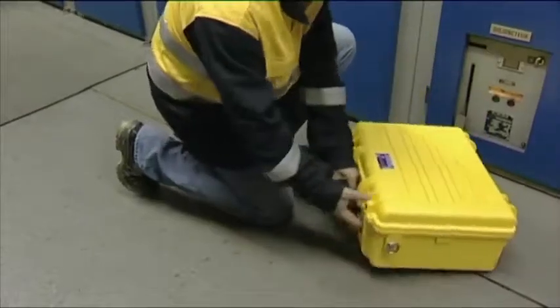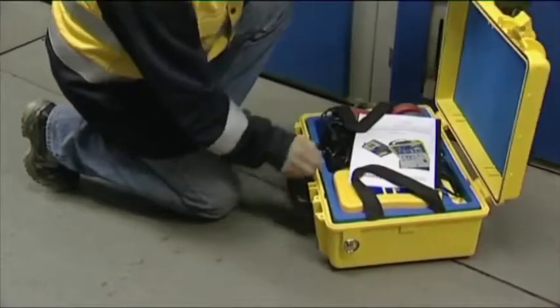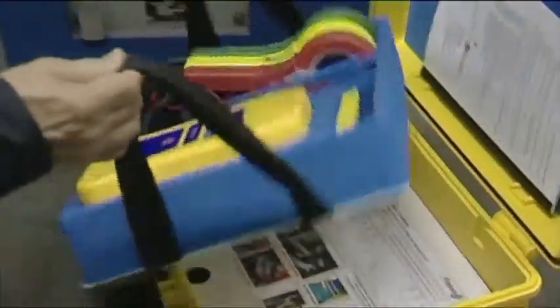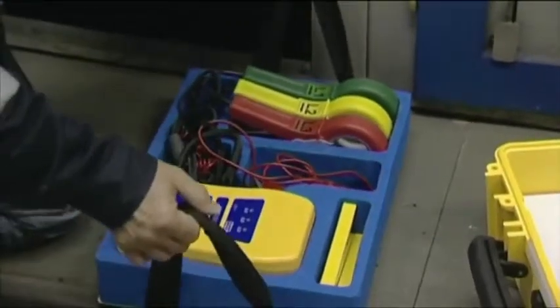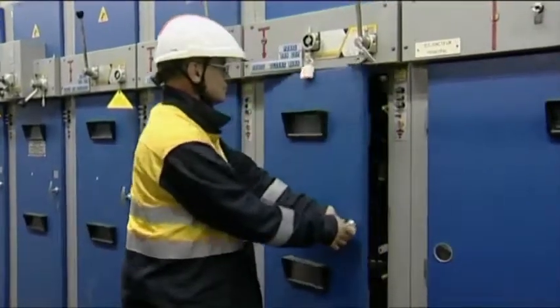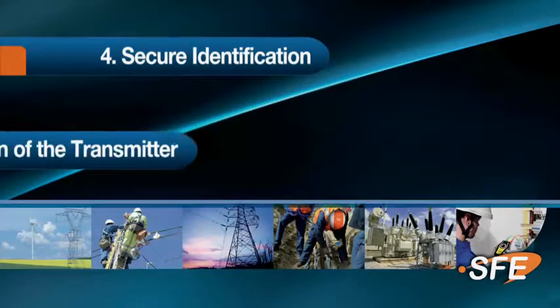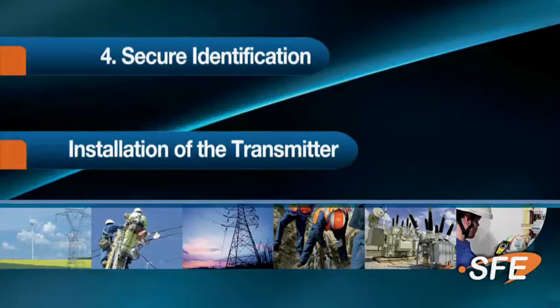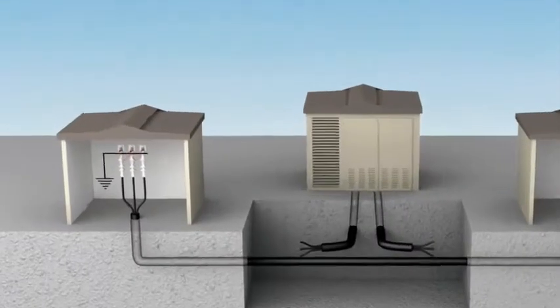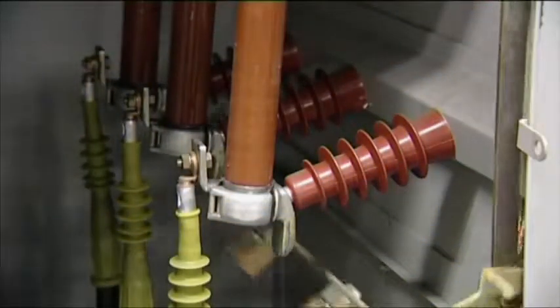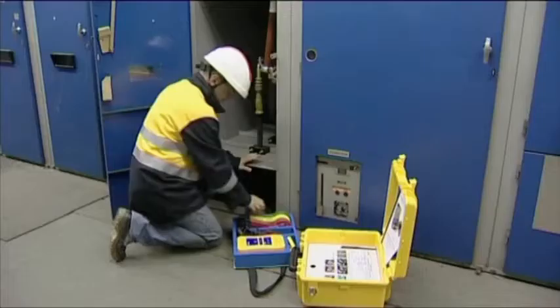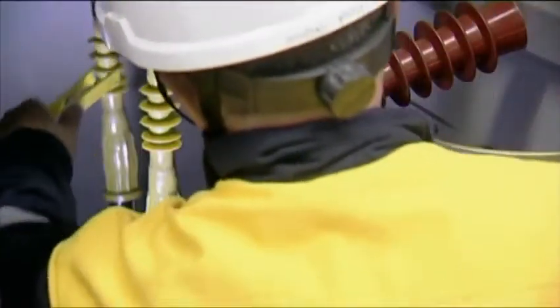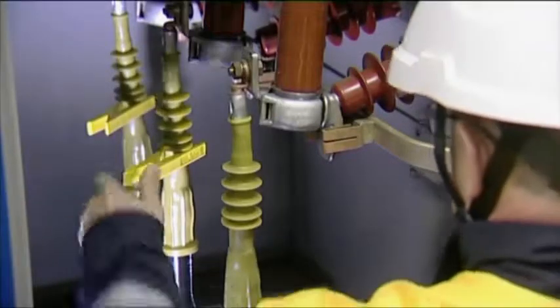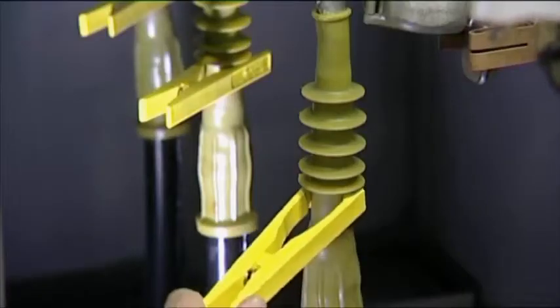We can now install the FC2300 identification device. The special feature of this electronic identifier is that it will function with the cable being grounded at both of its ends. But let's get back to the reasons behind this request. The operators wanted a way to identify cables that was compatible with safety procedures and grounding procedures in particular. In fact, removing grounding means additional back and forth at each stage when you're on the work site. And this is a more complex process that does not meet safety requirements and generates more risk.